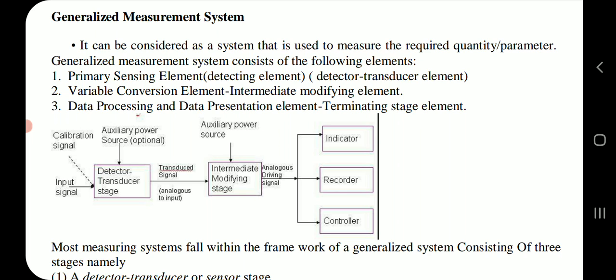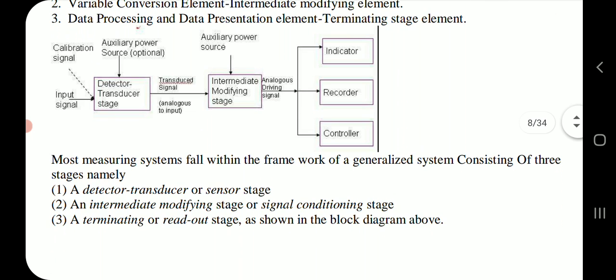Input signal, transducer signal, analogous to input, analogous driving signal, calibration signal, auxiliary power source optional, detector transducer stage, auxiliary power source, intermediate modifying stage, indicator, recorder, controller. Most measuring systems fall within the framework of a generalized system consisting of three stages, namely detector transducer or sensor stage, an intermediate modifying stage or signal conditioning stage, a terminating or readout stage as shown in the block diagram above.